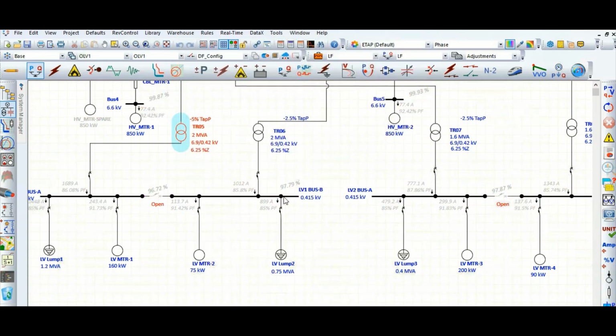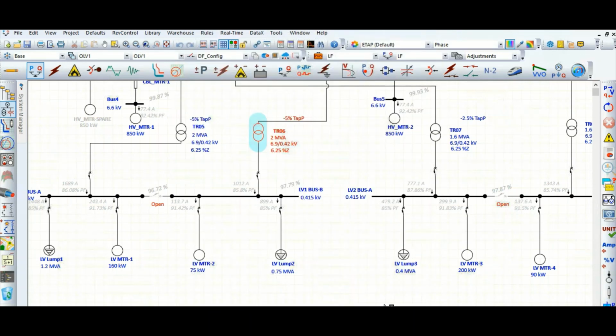If other loads connected with the respective bus or any other parameters cannot be changed, we can adjust by changing the transformer fixed tap position in this way. Now we can see the bus voltage profile is improved to 99% and 100%, so it's fine. Let's change for this also to minus 5%.